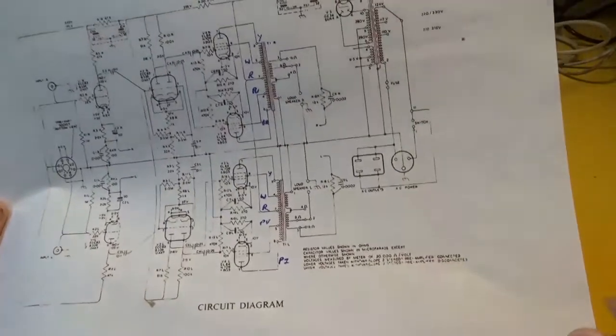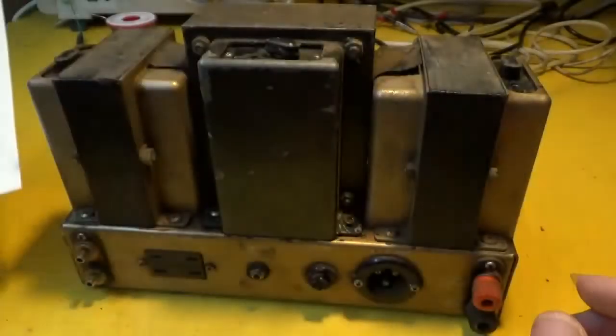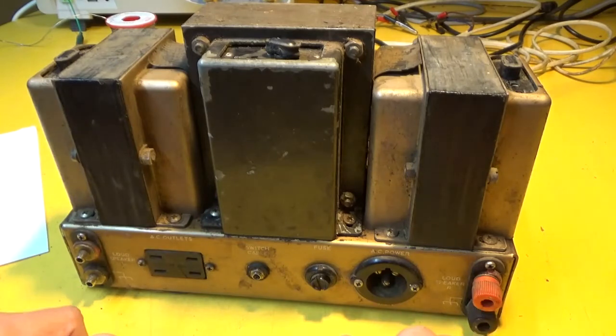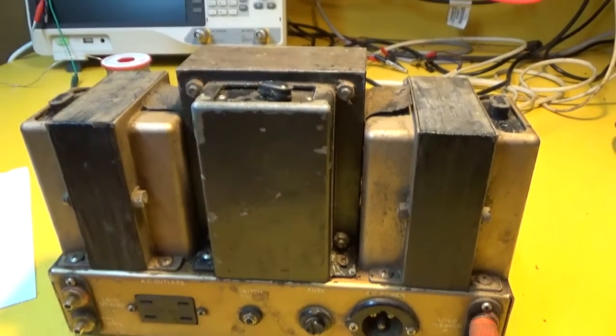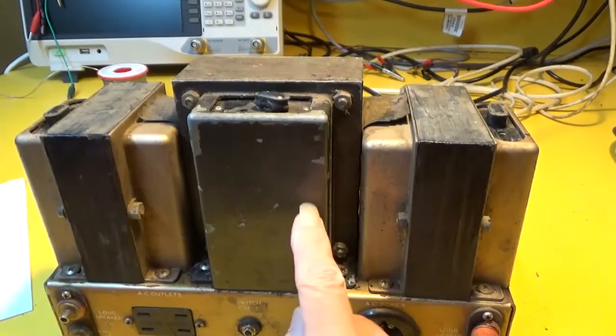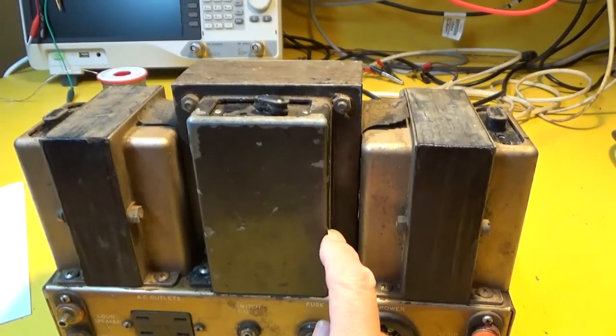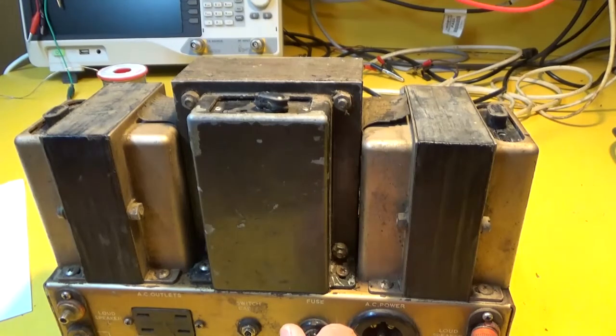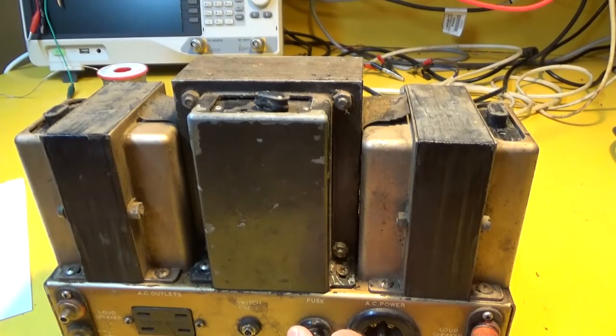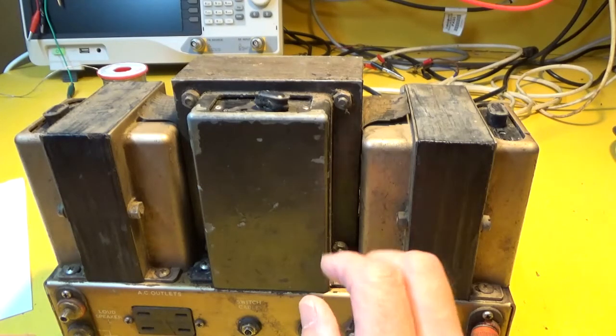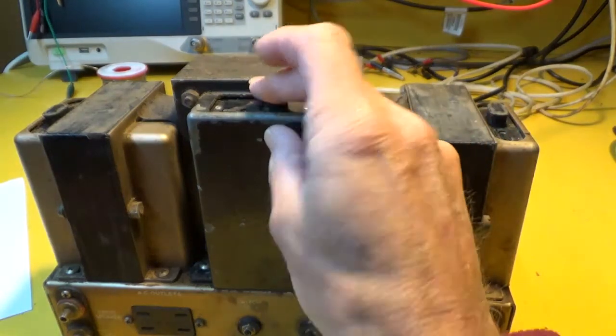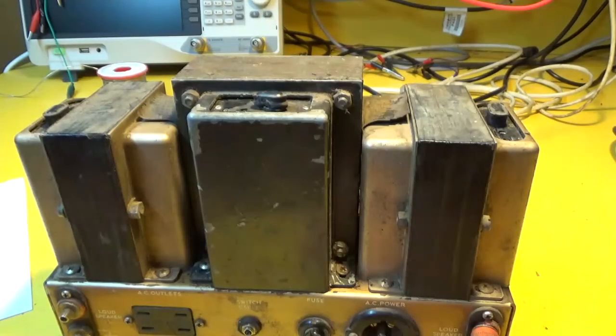Only time will tell. But the major problem with this thing, which is more serious than anything, is the mains transformer. I measured the primary resistance, and I was getting fluctuating readings between 4 and 12 ohms, and couldn't really find out why. It just seemed like there's an intermittent somewhere. Thought it was the main selector on the top, but that wasn't it.